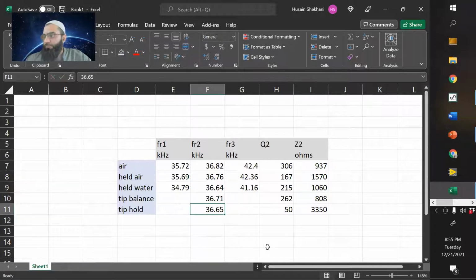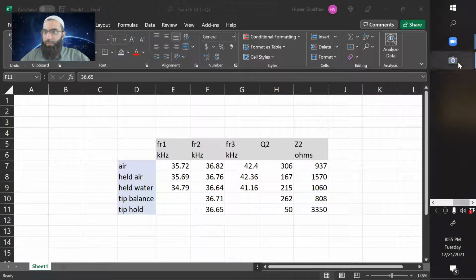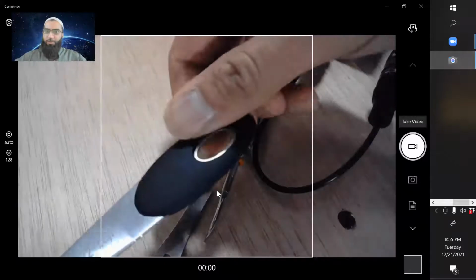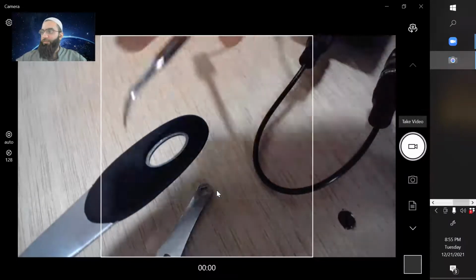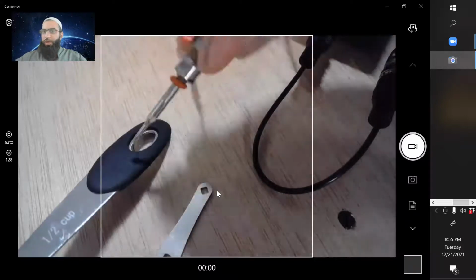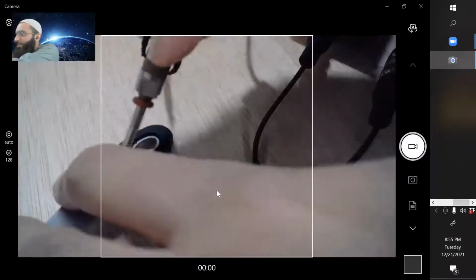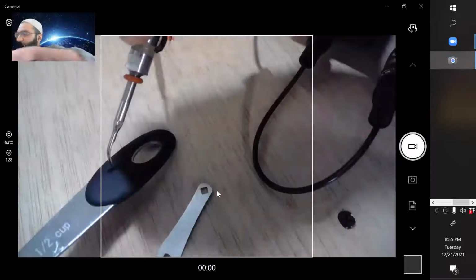In the final device, I would look for a situation where you can measure something like this. Not holding the tip is going to be kind of problematic. I'll give another recommendation. I'm going to pour the water back, and I will show, because holding it with your finger is not really a systematic way of doing it. This is actually a little bit rubbery, so it's kind of like a finger. So let's say you could load your transducer in a fixture or holder, and press the tip against the rubber surface with enough amplitude. Let's say press the back of the tip, like press it like this.